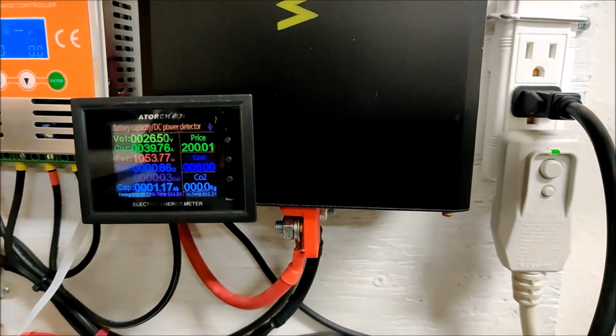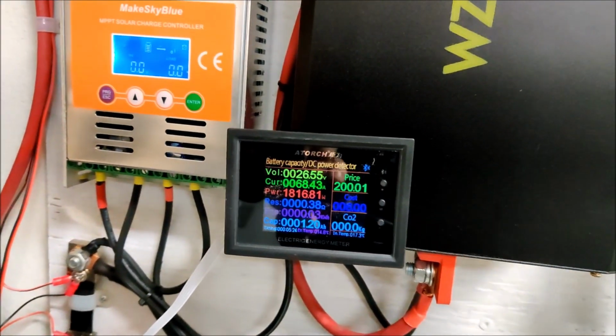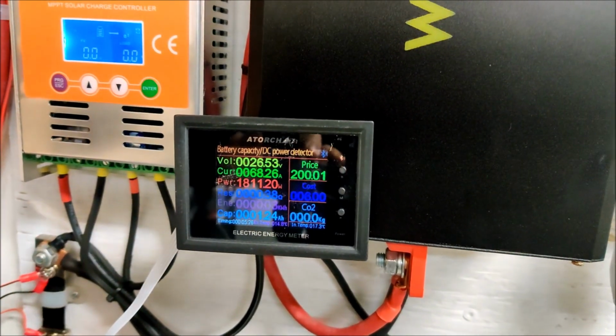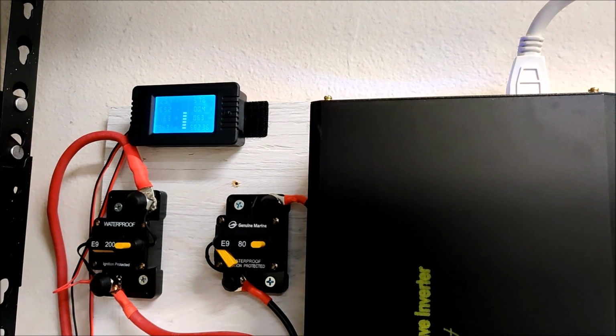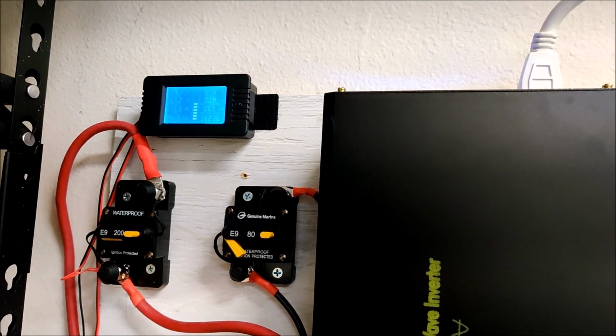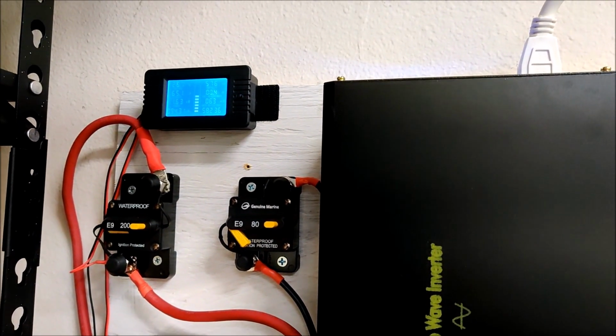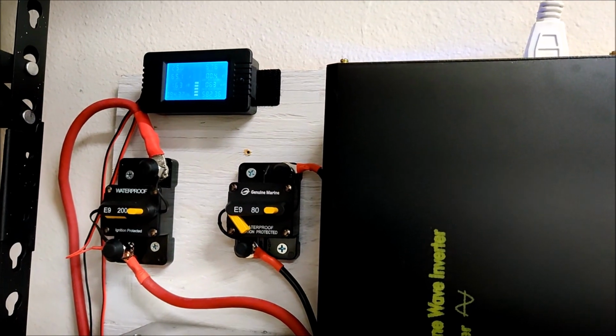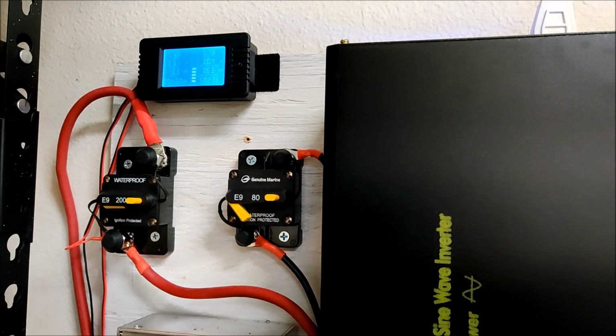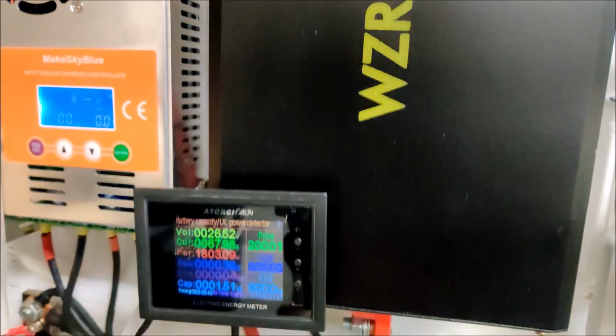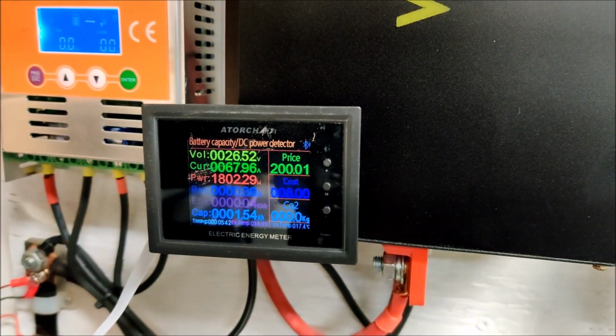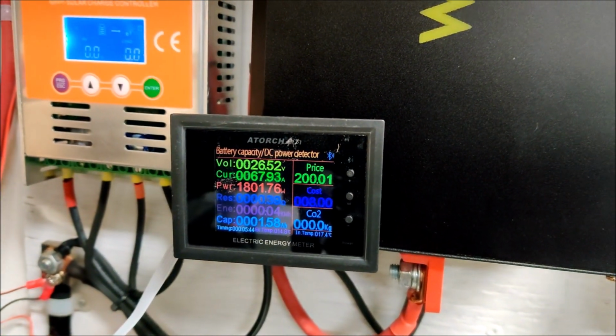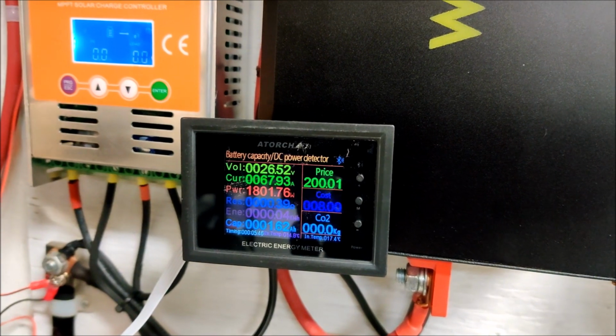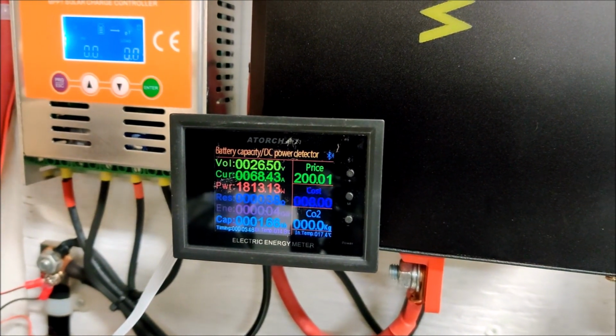Yet when I take it to 60 amps, my meter is saying 66, 65 amps, and that's 1 or 2 amps short, so it's really more like 67 amps. I've metered this with my clamp meter - it's about 67 amps. This meter also says 67 amps. So it's perfectly accurate at 60 amps.